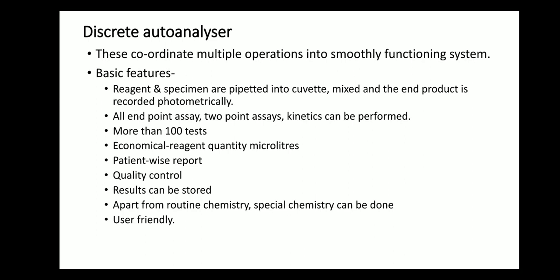So endpoint, 2 point assay, kinetics, everything can be performed using this discrete auto analyzer, and more than 100 tests can be done. Previously we saw either 1 or 6 to 12, but here in the discrete auto analyzer more than 100 tests we can do, and this is economical also.